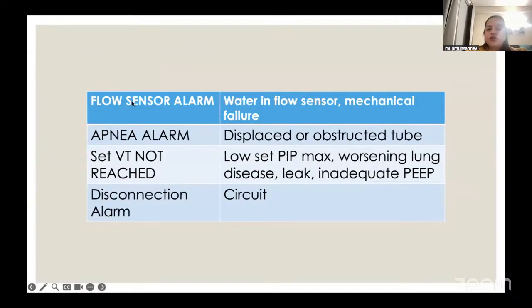A very common alarm is the flow sensor alarm. This commonly indicates that the flow sensor is not working adequately, and that is why the set tidal volume may not be delivered. This can be just water in the flow sensor or a complete failure of the flow sensor. In such cases, we should first recalibrate the flow sensor and change it if required. The apnea alarm. Many of us would think that the apnea alarm simply indicates that the baby doesn't have its own respiratory efforts and is being treated with all the mechanical backup breaths, but it's not just that. The apnea alarm may sometimes just indicate that the tube is not in its correct position and is either displaced or obstructed.